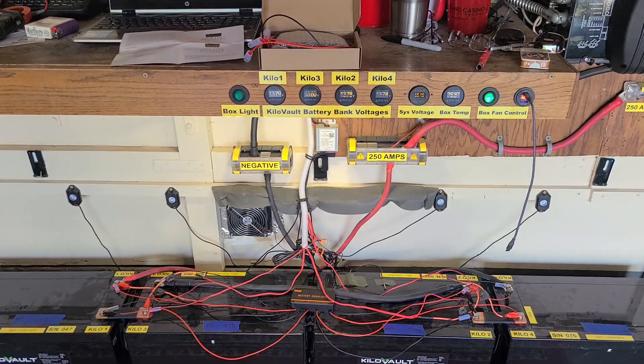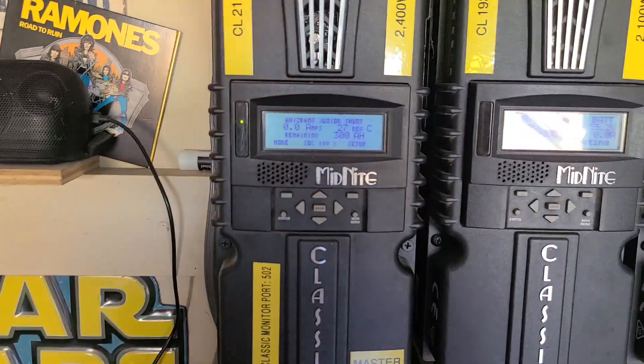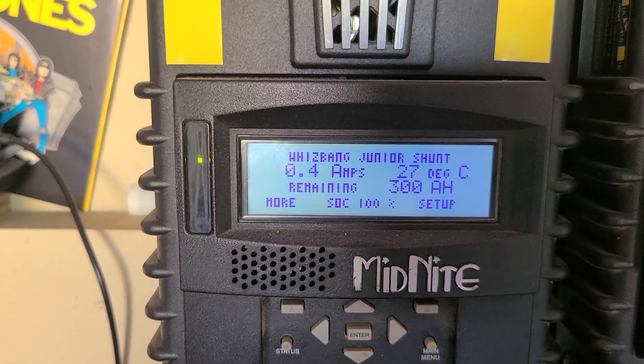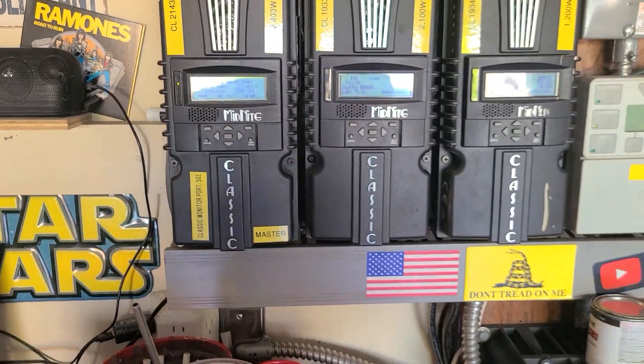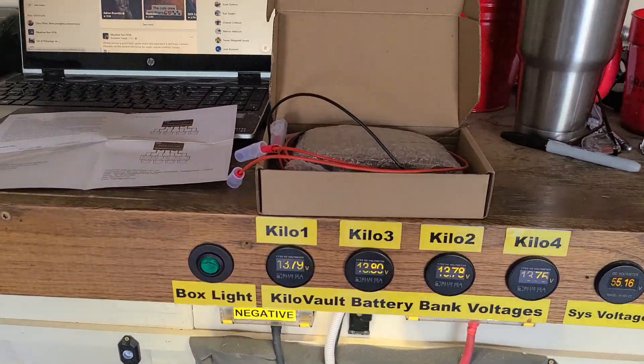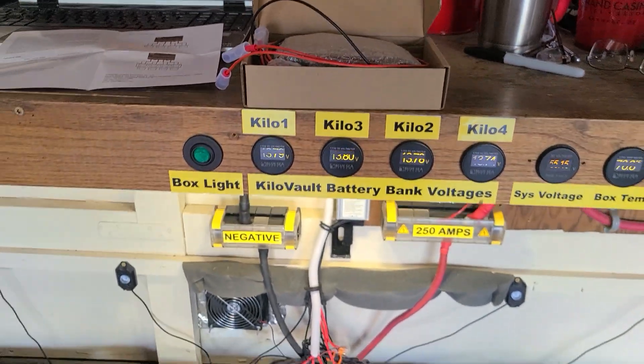I set the absorb and bulk charging per the KiloVault specs up here. There's nothing connected and the inverter is off right now, so it's just idle quiescent amperage — just enough power to run the electronics in there. It's done charging, and it's sitting about five one-hundredths of a volt off. That is awesome.